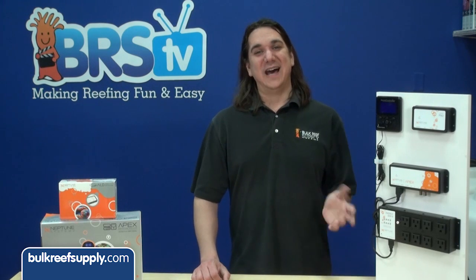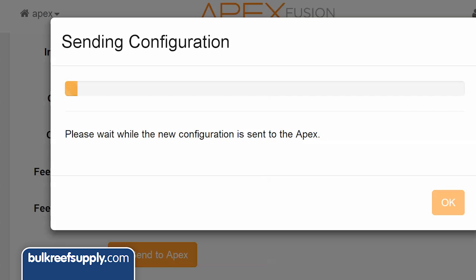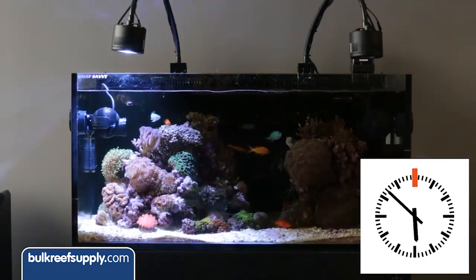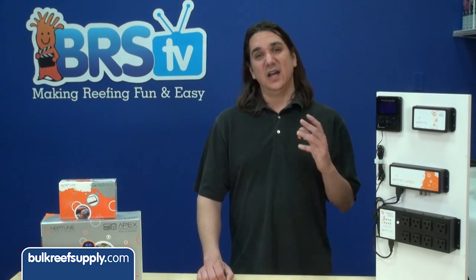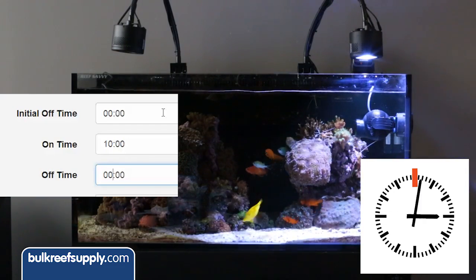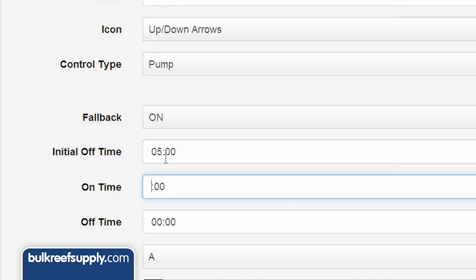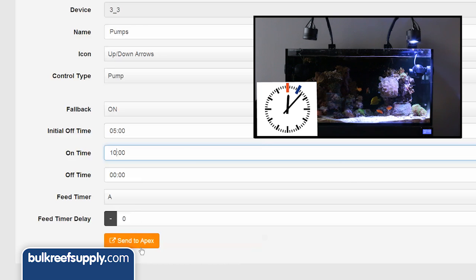There is one component to this that is not obvious and needs to be understood before we can move forward. The initial off time is not from the moment you hit the send button. What we are doing is creating a cycle that will start at the beginning of the day, which is midnight, cycle through the three on/off cycles here, and repeat itself throughout the entire day. So if I set the initial off time to five minutes and the on time to basically anything, the cycle would start at midnight with the pump off from midnight to 12:05, at which time the pump will turn on.